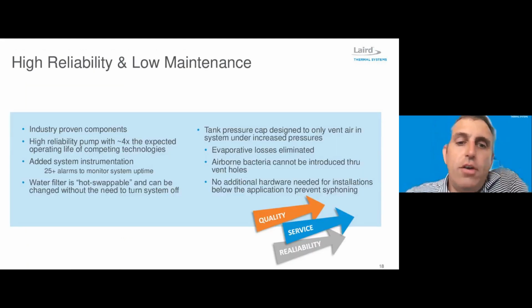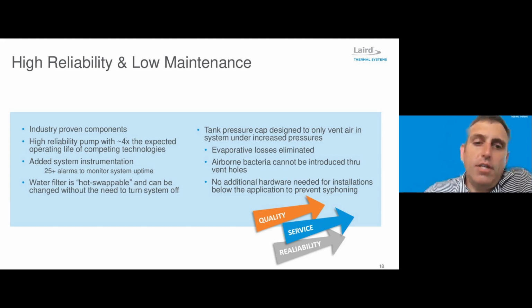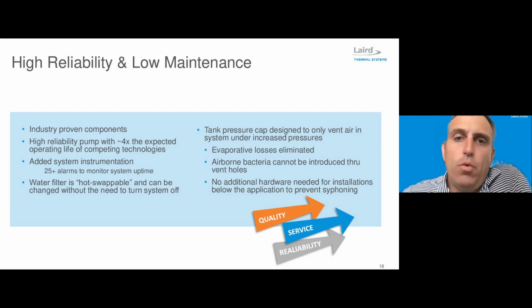So when we look at what this product offers in terms of reliability and maintenance, I mentioned the proven components and suppliers, technologies within the industry that we use. We also use, of those suppliers, some of their technologies that are very reliable. So the pump, for example, is what's called a turbine pump. It's a regenerative turbine, which has near zero wear parts in the pump itself. This gives us about 4 times the expected life of some of the competing technologies in the market. We also have a lot of instrumentation put into the system so that we can monitor the operation and the health of the system over its lifetime. There are about 25 alarms that can indicate something is starting to go wrong, so that we can get attention in order to prevent unwanted downtime.